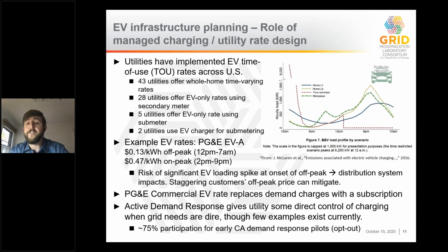What that has the potential to do is shown in this figure. This is a travel-survey-based model of electric vehicle charging, assuming the charging equipment that exists at home. If you look at level 2 charging, there's a peak if unmanaged around 7 p.m. If instead you defer all charging for a period, which is easy to do and would happen with a time of use rate, that peak in aggregate from many vehicles can be up to 4 times as high, but it'd be at midnight. So there's a risk that you create a shock to the distribution system that should be managed. This is once EVs are at scale, and this is only EV load.